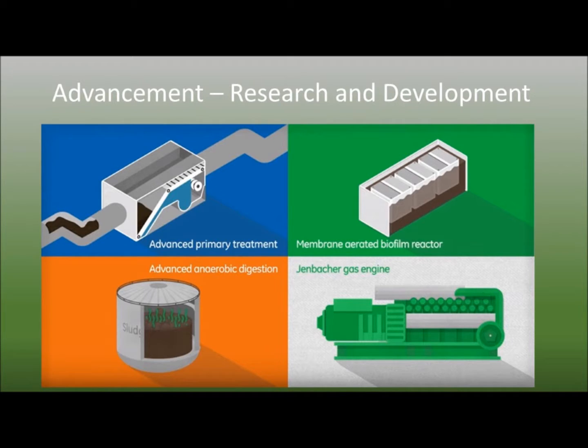However, currently many of these engines are experiencing premature wear when used at wastewater treatment plants. Siloxanes within the fuel are causing deposition of silicon dioxide when burned. These siloxanes originate from products such as shampoos and lotions, which is why they are present in the wastewater. Research is currently being conducted on the effectiveness of various filtration methods for the removal of these siloxanes.